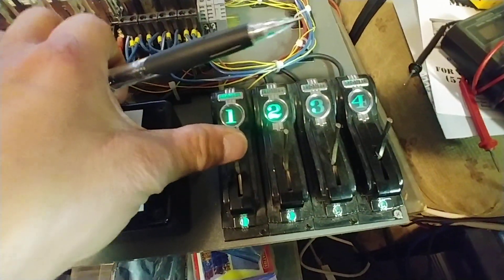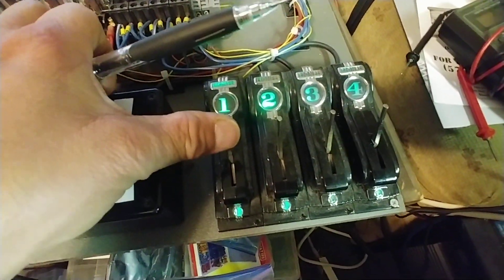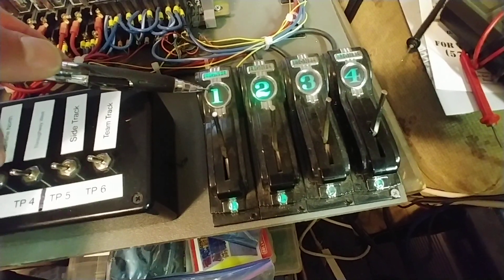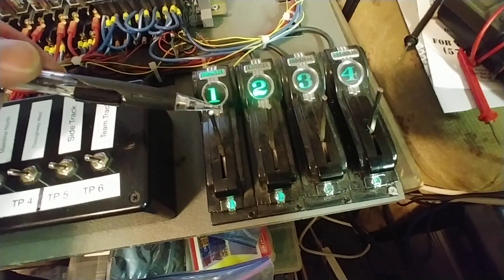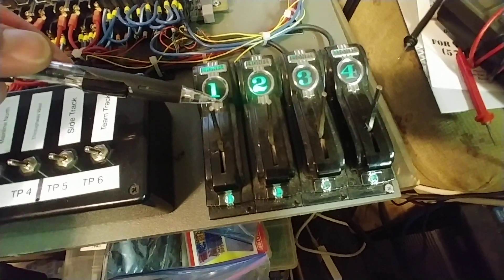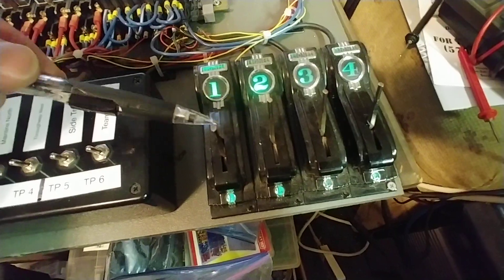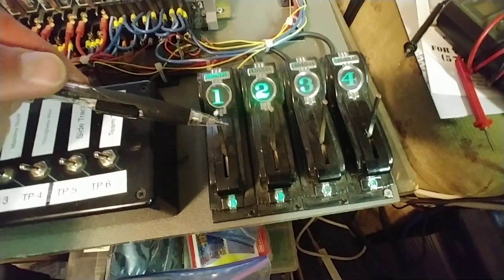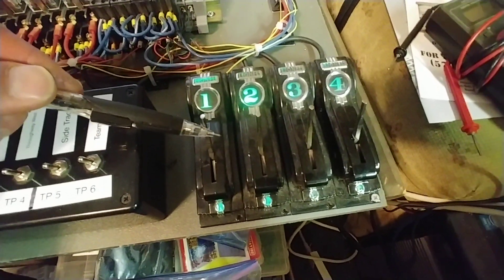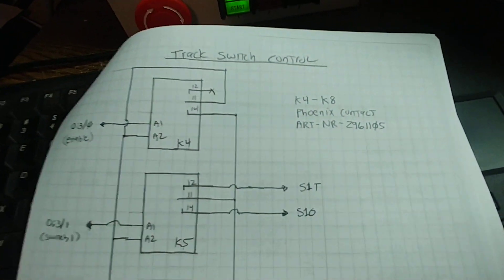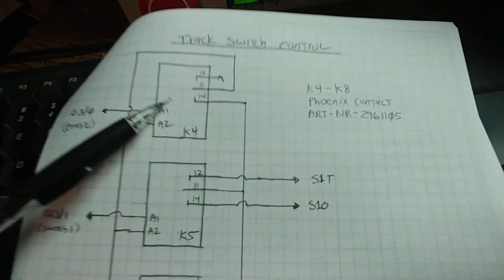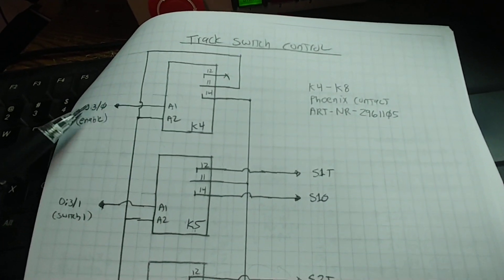But if it was in manual mode, if you continue to try to close that switch - as long as it indicates it's latched, nothing's going to happen. But if it isn't, then it's going to try to drive that motor. So it was designed, even in the original project, to have this relay first, which is called the enable.